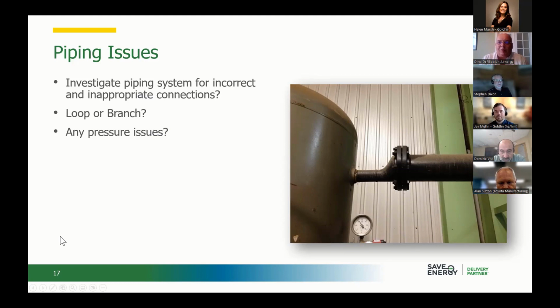That's correct. So that original picture where you saw the compressor room with the three compressors, this was actually the wet receiver that was installed. For whatever reason, no one was able to explain to me why we had a 6-inch header into a 2-inch air receiver connection. That was the choke point. They were having issues with pressure downstream. They felt that they had to run all the compressors, and as I followed the receivers, obviously that's the first thing that the light bulb goes off, and the recommendation was get rid of it and put a properly sized air receiver with proper size connections.